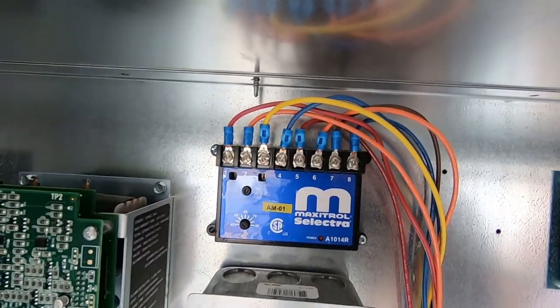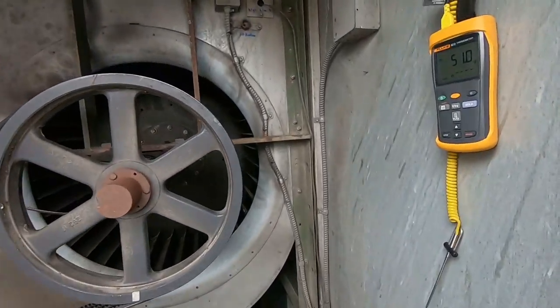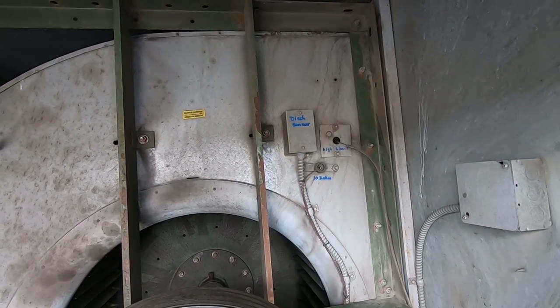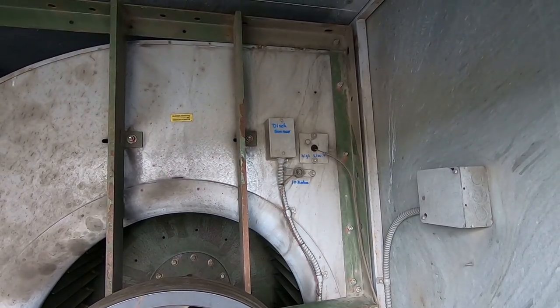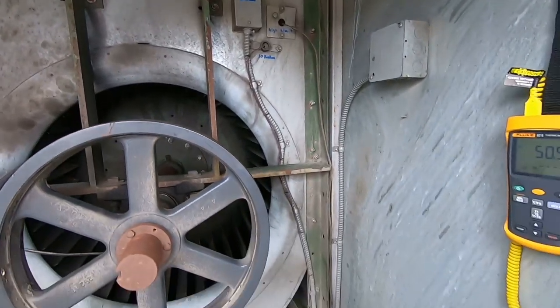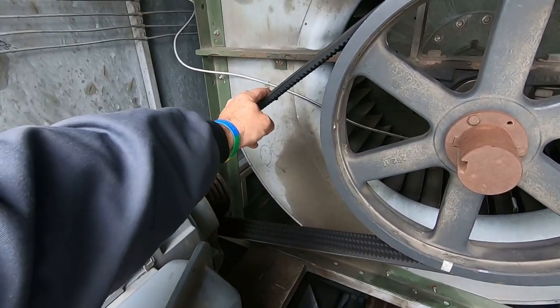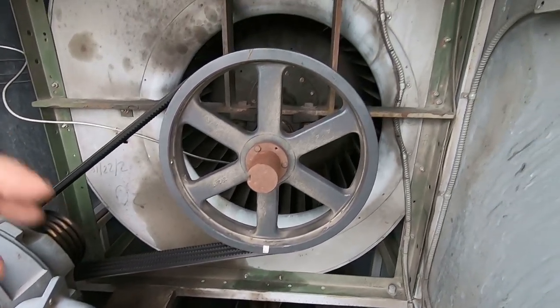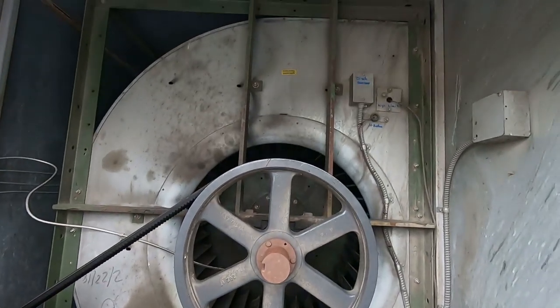But if you go over to three and four, that is going to your discharge sensor which is up here on top. I pulled that sensor out, made sure my tube was clean, checked my ambient temperatures and it was off also. So they're going to send me a new one of those. Discharge sensor's out of whack, the temperature adjustment on the inside was also out of whack. So all those things combined, along with cleaning the burners out with nitrogen, making sure the filters are clean, belts being loose. I mean that's pretty much it. But you know, three, four things all combined together. Once we get those things here, we'll put them in and then everything will be jim dandy.